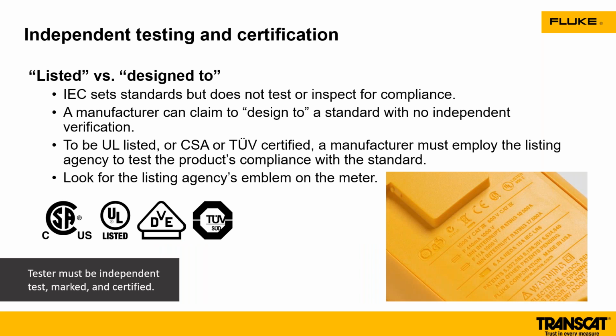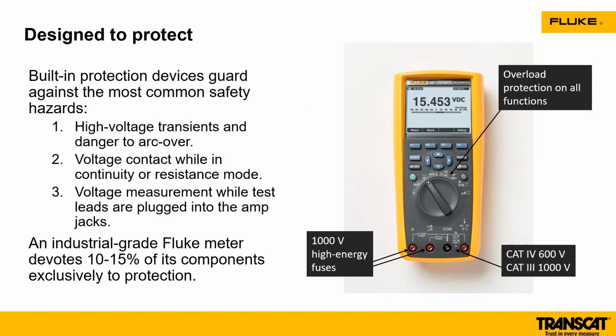Also, make sure that the products you're using have been tested and certified. That's another safety win in this conversation. Make sure that it has that CSA or UL listing on it. These are key because they've gone through a third-party independent certification. They've been tested, and the manufacturer validates that that meter's qualified and meets that IEC 61010 standard. So that's a big win as well, because these meters are truly designed to protect you. Again, this is part of your PPE.